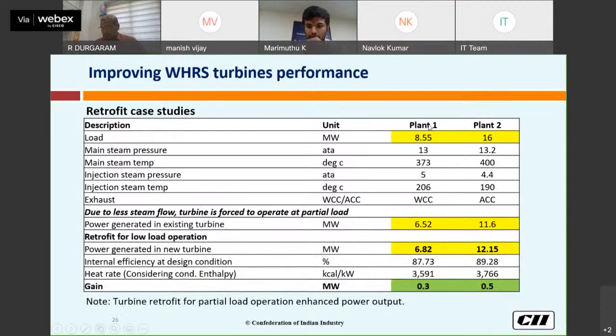So you can see the figure, plant 1 and plant 2. It was designed for around 8.55 megawatt, but it has to operate at 6.52 due to low generation. Generally, if the load factor of the turbine is less, it will reduce the efficiency. So to operate at low load, the turbine was retrofitted. With the same steam flow, which was generating 6.52, after retrofitting it has given around 6.82.